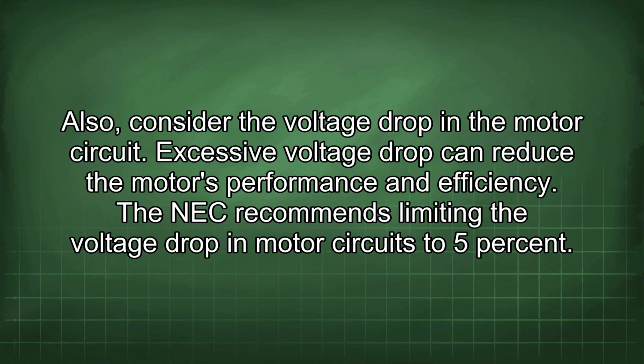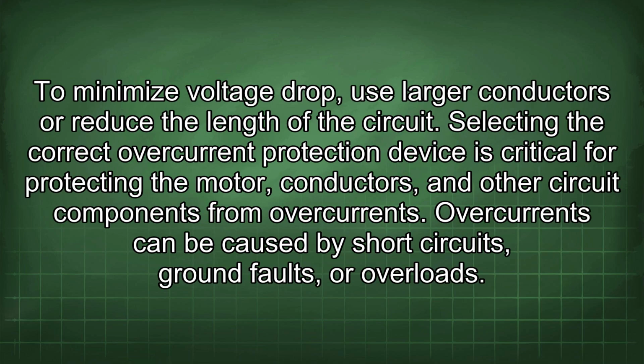Also, consider the voltage drop in the motor circuit. Excessive voltage drop can reduce the motor's performance and efficiency. The NEC recommends limiting the voltage drop in motor circuits to 5%. To minimize voltage drop, use larger conductors or reduce the length of the circuit.